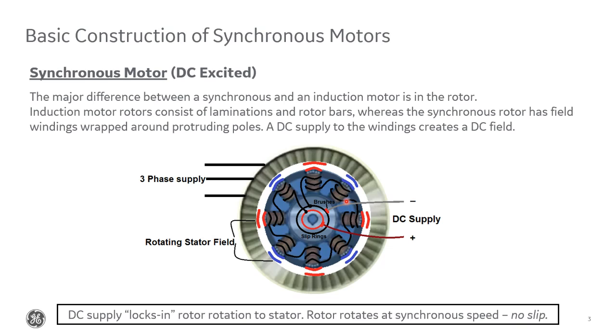So these rotor windings are connected to a DC source like we show here. The purpose of this DC source is to maintain the magnetism for the rotor windings. So here we're not relying on the stator to magnetize the rotor during operation. The DC supply is adjusted to keep the rotor windings magnetically locked in to the stator so that they rotate together in unison. So in this case, the rotor operates at synchronous speed matched with the stator. There's no slip and the speed is generally not affected by loading, which is one of the main benefits to using this type of a motor.